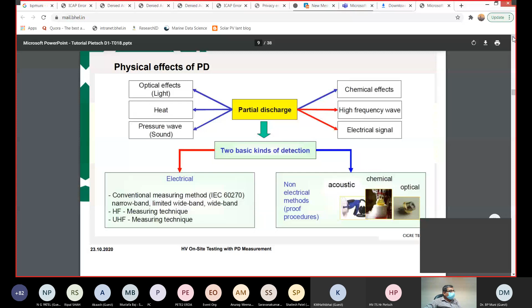Here you see why I can answer: at the bottom, you have the PD, the device which analyzes, but this depends on the discharge itself. Is it a hopping particle? Is it a delamination? Is it a void inside a transformer? Then it depends on the distribution and traveling of the wave to the sensor. And then, like the UHF questions several minutes before, which UHF sensor is suitable defines the sensitivity. Therefore, there's no reason to define this equipment as better. You have to look at the whole path of the signal.